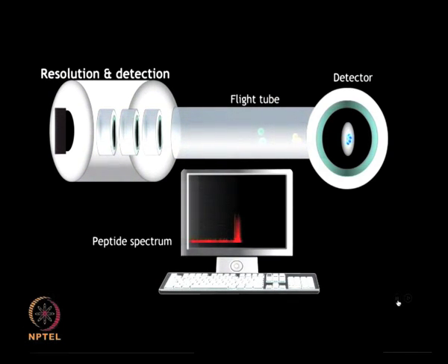These ions are resolved and detected on the basis of their mass to charge ratio, and a mass spectrum is generated. Parameters such as geometric design, power supply quality, calibration method, sample morphology, ion beam velocity, etc. all affect the accuracy of mass detection.